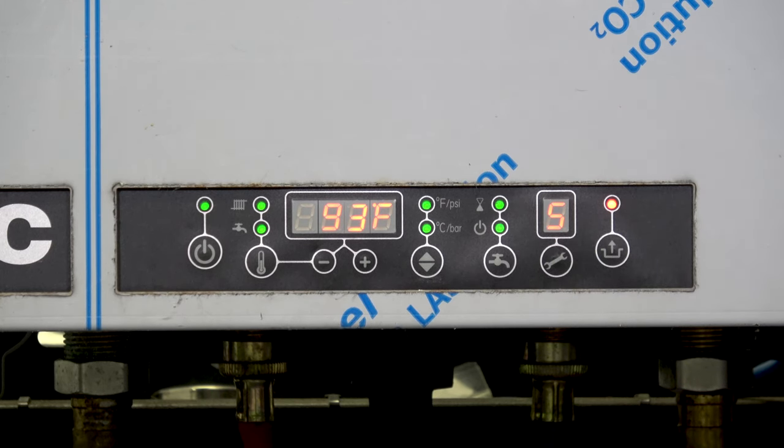As this boiler comes out of the box, the presets are suited for a copper baseboard system — it's set for a high temperature system. If you're putting it into a radiant application or using hot water radiators, you may want to change some of these settings. In this case, we're going to set it to 125 degrees for copper baseboard. Once we've set that to 125, we press the wrench or Enter button.